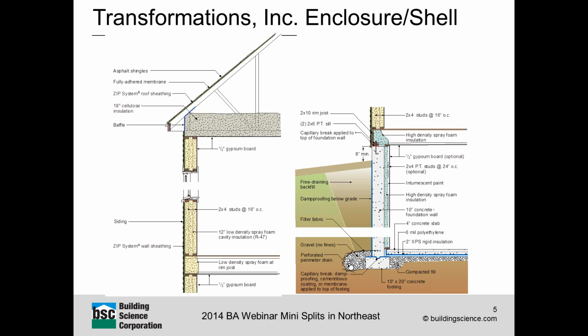Another nice thing about mini splits is that they modulate to meet load. Basically, they ramp their fan speeds and compressor speeds up and down based on how much load they're facing, what the outdoor conditions and indoor conditions are. One thing that's found if you look at the ratings is that the best performance you can get out of these units is at part load, and they're the worst at full load. Basically, if they're chugging along at full load, they're at their lowest efficiency point.